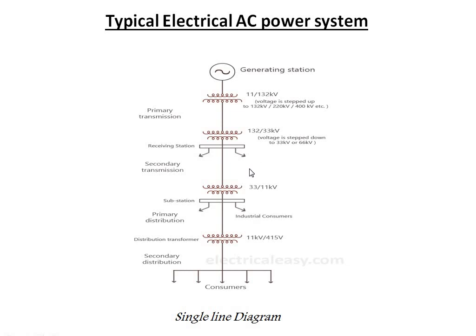At the distribution side, the voltage is reduced from 11 kV to 415 V. For three-phase consumers it will be 415 V, and for single-phase consumers it will be 230 V. In this video I have explained the general electrical power system and described a single line diagram showing the voltage levels at each stage from generation through to the consumer.